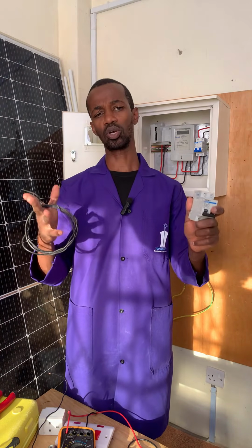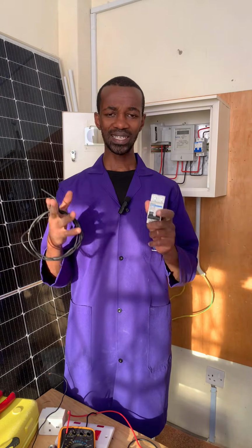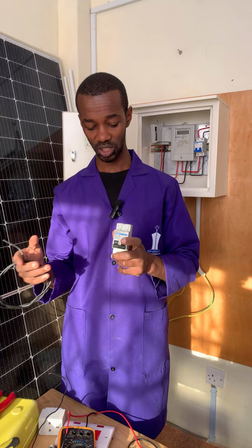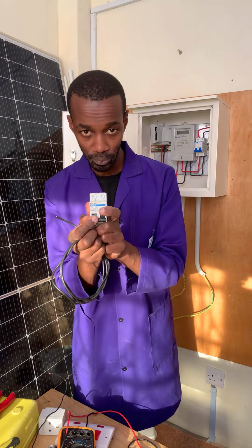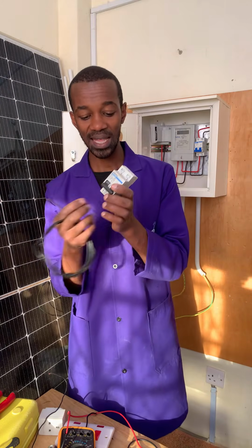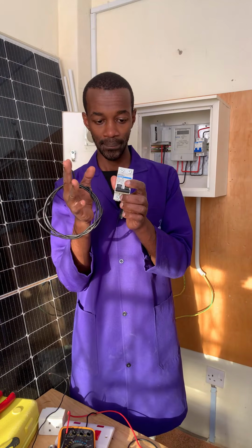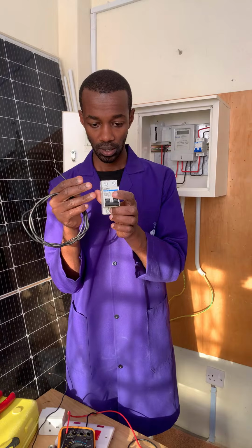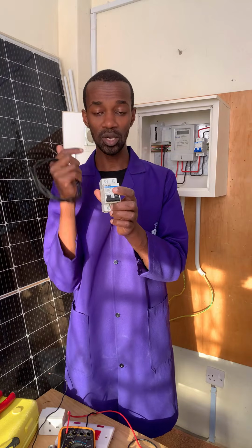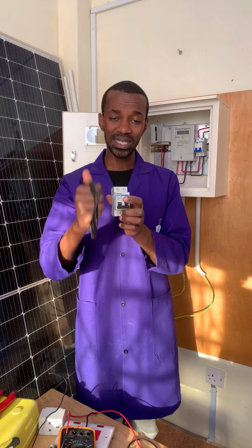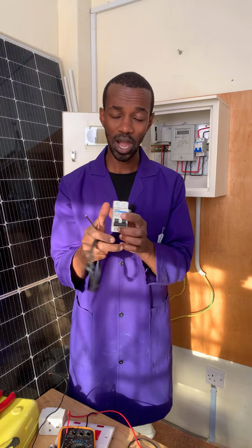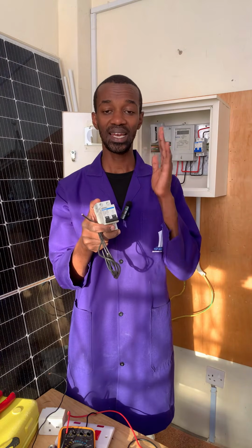But you will ask me, John, how do you switch it off and yet you are testing for the voltage? Yes, you switch it off so that you can isolate the loads, and then the incoming line, you can isolate it, because remember, always isolate the neutral after you have isolated the line.